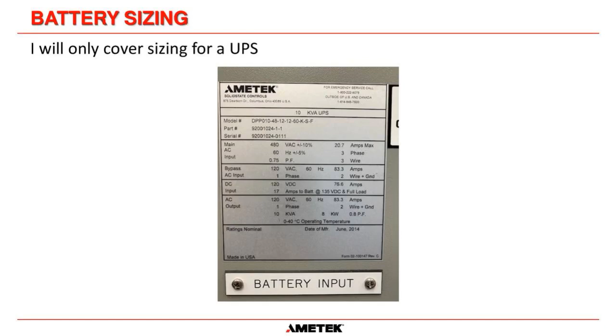So here is the rating plate for an AMETEK 10 kVA UPS. Now, if you go down to the DC input section here, it says that at full load, we're going to need 76.6 amps. So to get 10 kVA, we're going to need 76.6 amps.